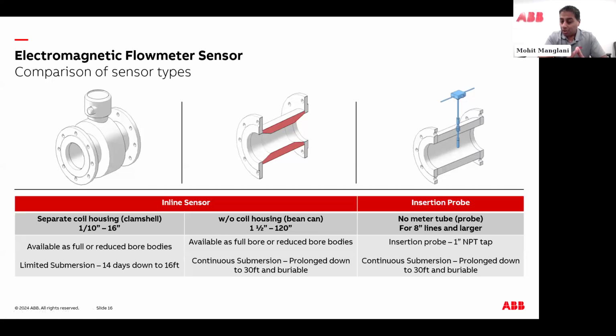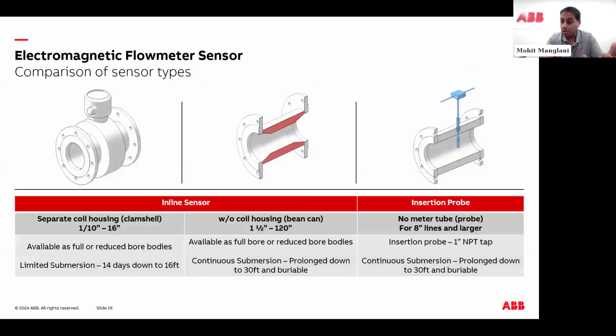In a lot of mag meter applications, especially in the municipal market, there are a lot of pumping stations and lift stations. There are a lot of outdoor installations that go underwater. You have basements that can get flooded, and you have pits. So the idea is that you want to maintain submersion capability, and make sure it's rated for IP68 submersion.